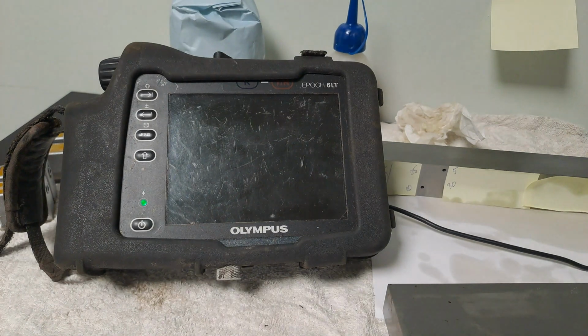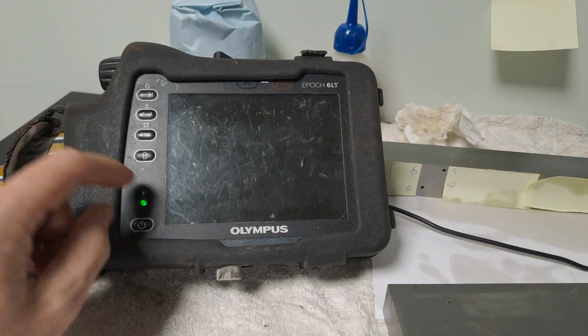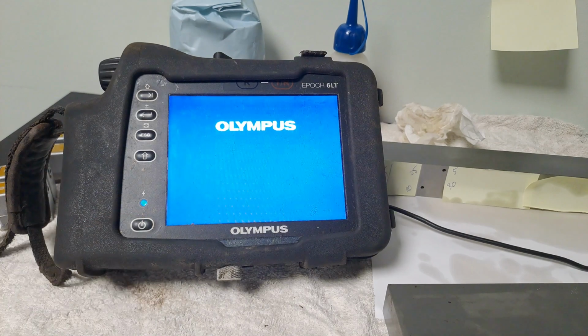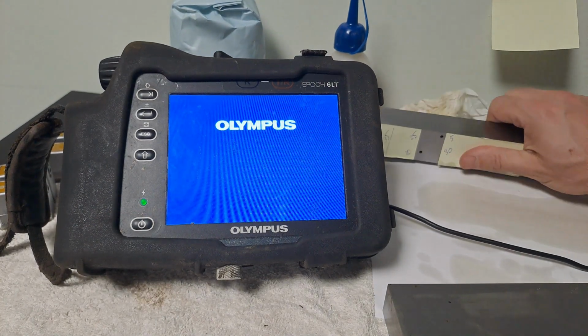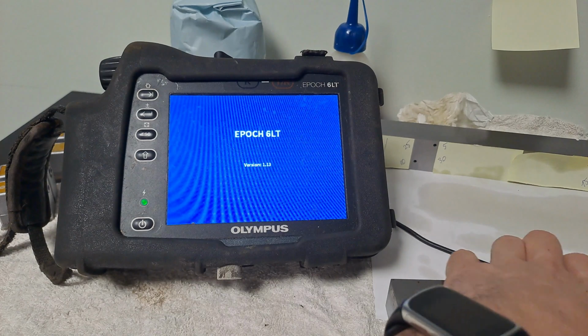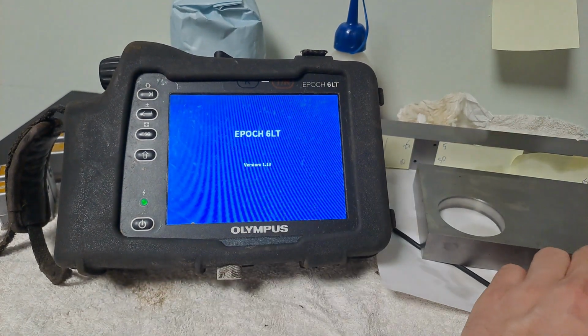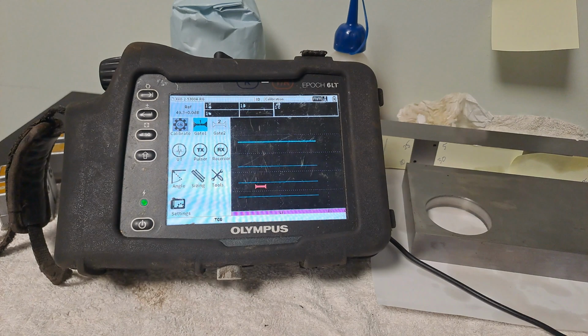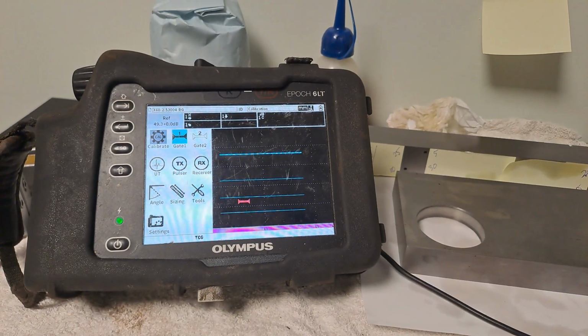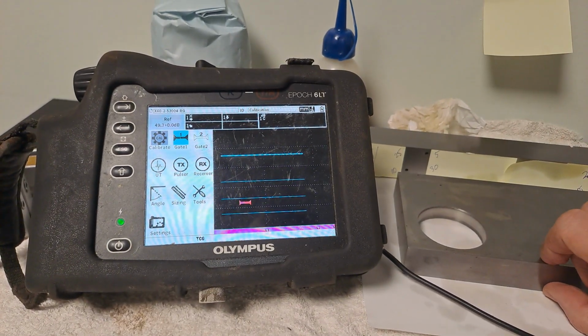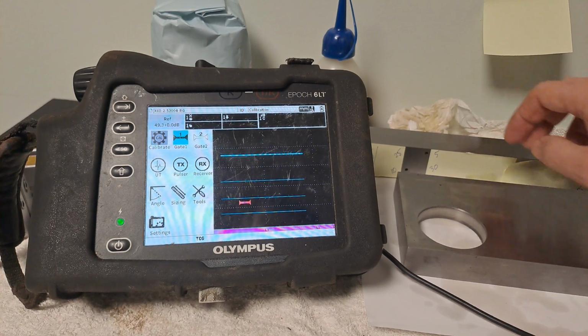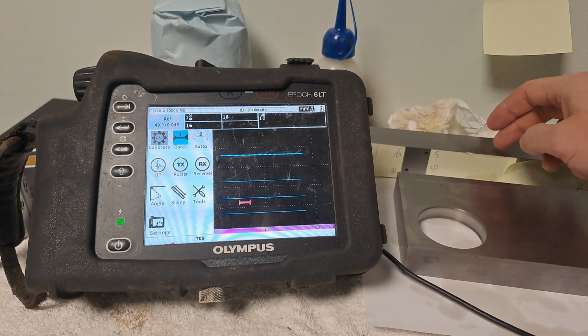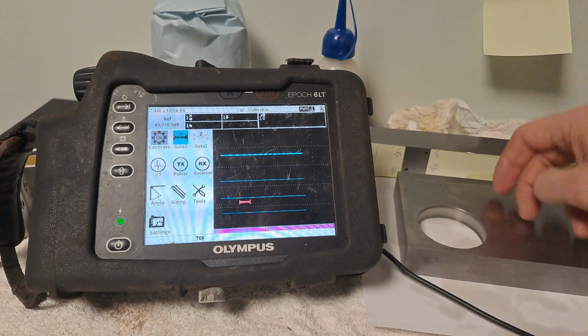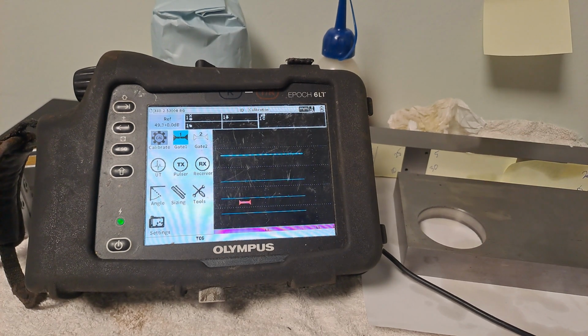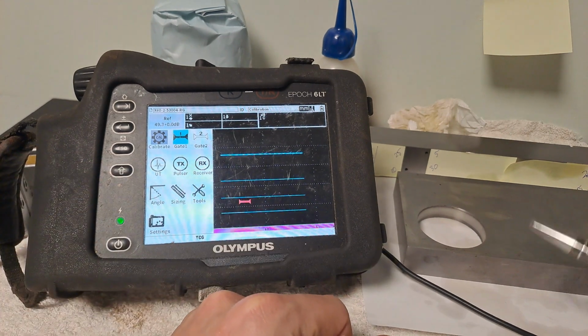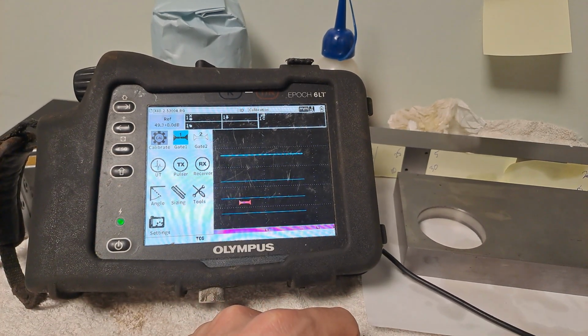What we need is the machine. Here you go, it's already charged. I will use the number 1 calibration block, but then that's too thin, so we'll put on this, maybe do the transfer correction, check if that one and that one is the same. Okay, and then what else? That's it.